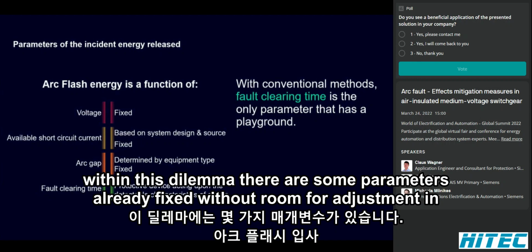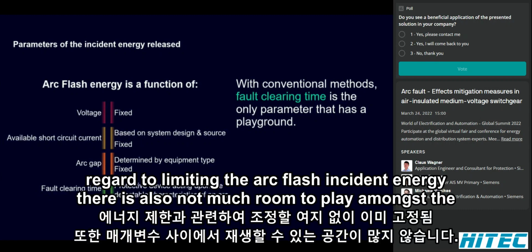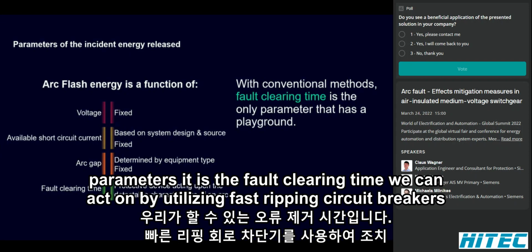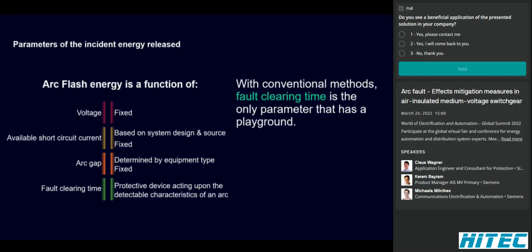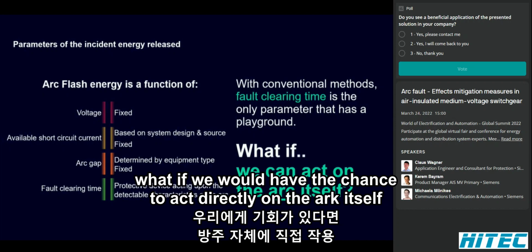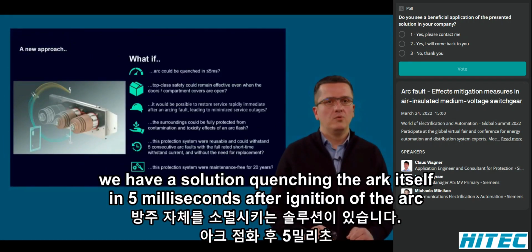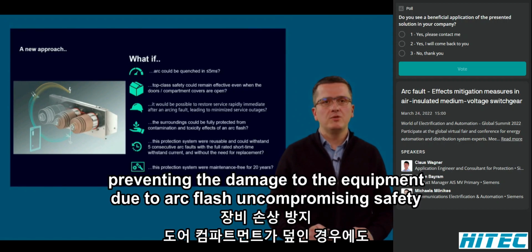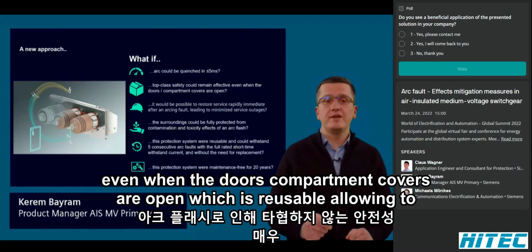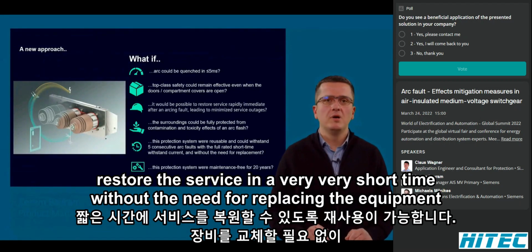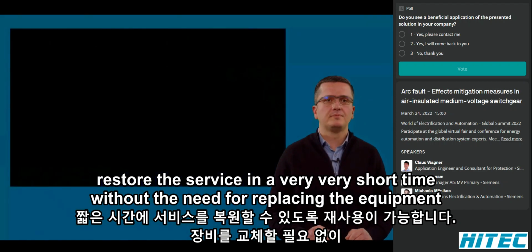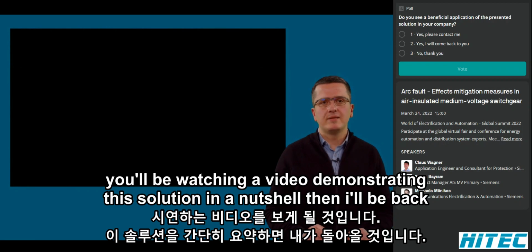Within this dilemma, there are some parameters already fixed without room for adjustment. In regard to limiting the arc flash incident energy, there is also not much room to play. Amongst the parameters, it is the fault clearing time we can act on by utilizing fast tripping circuit breakers and early detection of arc via light or pressure sensors. What if we would have the chance to act directly on the arc itself? We have a solution, quenching the arc itself in 5 milliseconds after ignition of the arc, preventing the damage to the equipment due to arc flash, uncompromising safety even when the doors and compartment covers are open, which is reusable, allowing to restore the service in a very, very short time without the need for replacing the equipment. You'll be watching a video demonstrating this solution in a nutshell. Then I'll be back.